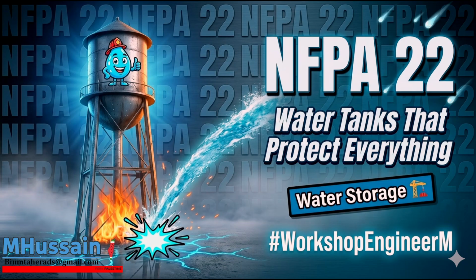Got it. But here is the critical step. You must select a physical tank volume that is significantly larger than your actual water demand. You need that extra empty volume to hold the compressed air. And then you use the ideal gas law. Exactly. Once you have your total volume and your water volume, you calculate the starting pressure required to achieve that final discharge pressure. But there's a massive engineering constraint hidden in that calculation.